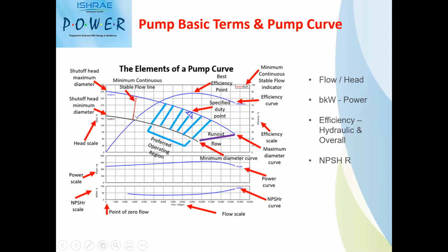That is also marked here, or we can guess the point based on the efficiency levels, wherein we try to have, say, minimum 45-50% efficiency of the pump, with which the pump has to be run. And then we have something called the power curve, which is typically shown here, or generally power curves are also shown in the single curve itself. This power curve ranges from 0 to the maximum flow of the pump, and power keeps on increasing as you start drawing more flow from the pump. So this is the power curve with respect to your flow as well as head.